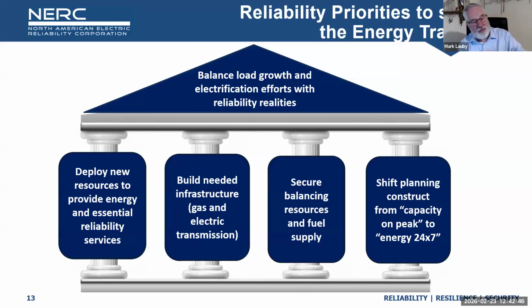Well, the large load was looking at these voltage depressions and saying, well, that's it then. I'm getting out of here because I've got to preserve my refrigeration or my cooling for my site. And so they just disconnected 1,700 megawatts and went to their backup generators and kept running. So the load went away, even though it's still running. And then, of course, that shook up the system a bit.